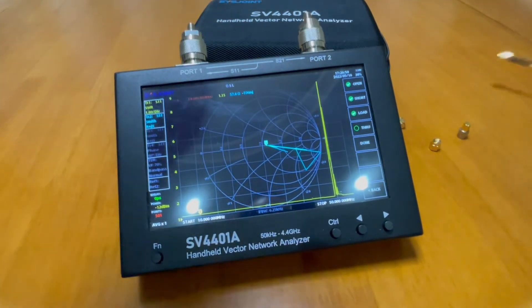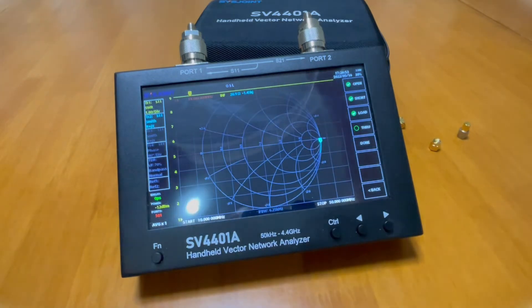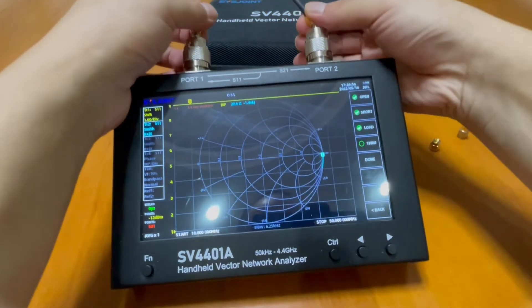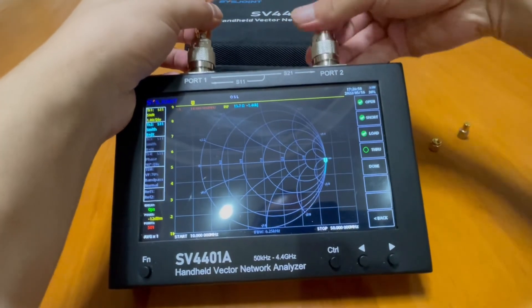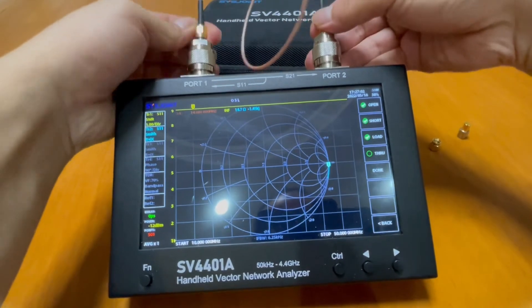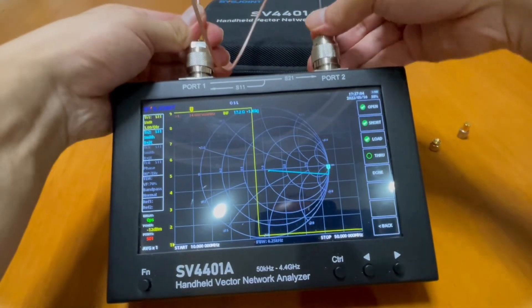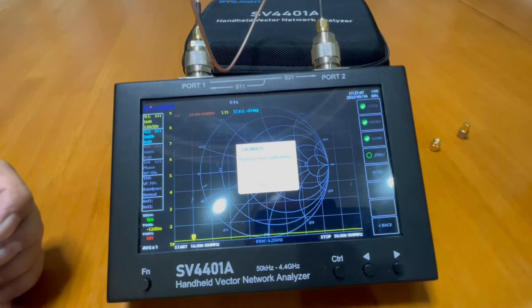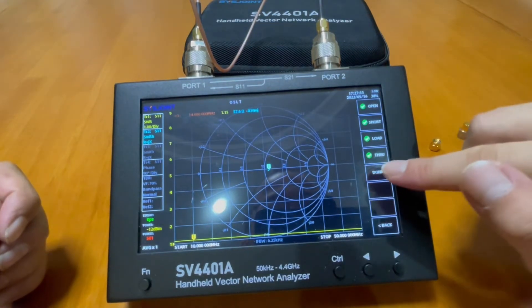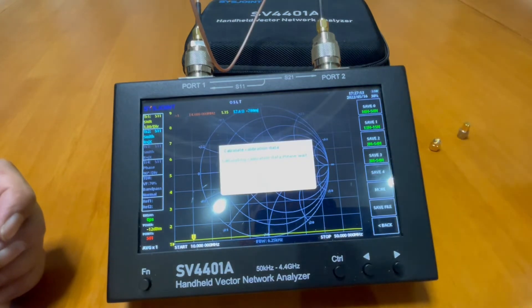For the through calibration, what you need to do is put the cable provided to the two ports, connect to the two ports, and click through. Now the calibration is done and you can click done.